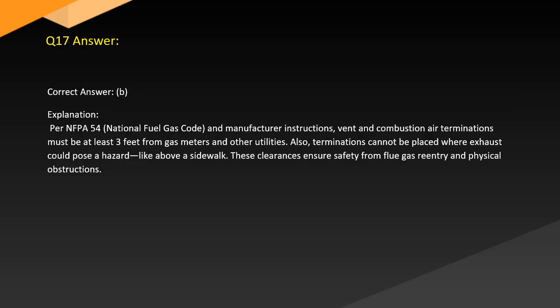Answer. Correct answer: B. Explanation. Per NFPA 54 National Fuel Gas Code and manufacturer instructions, vent and combustion air terminations must be at least 3 feet from gas meters and other utilities. Also, terminations cannot be placed where exhaust could pose a hazard, like above a sidewalk. These clearances ensure safety from flue gas re-entry and physical obstructions.